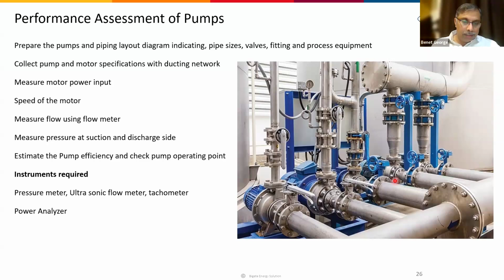And this is one method, an ultrasonic flow meter. If it is not available, you can also use other methods. For example, if it is pumping to a tank, you can measure the area of the tank and how much the water height rises over a specific period of time. Based on that, we can find out the water flow. Or you can use a calibrated drum or calibrated bucket, measuring how much water flows every minute or every second, and from that find out the flow in cubic meters per hour. Then for power, you can measure using a clamp-on power meter, or a portable power meter.